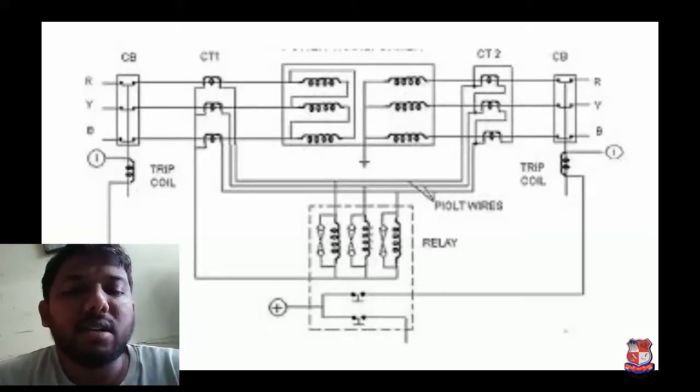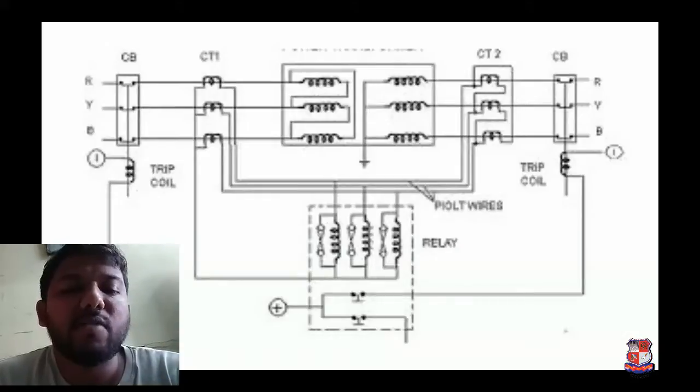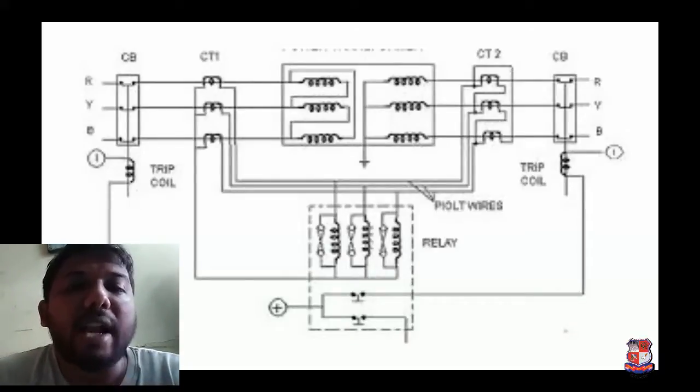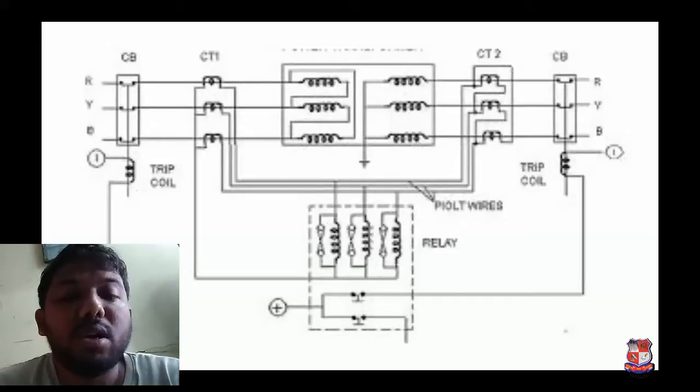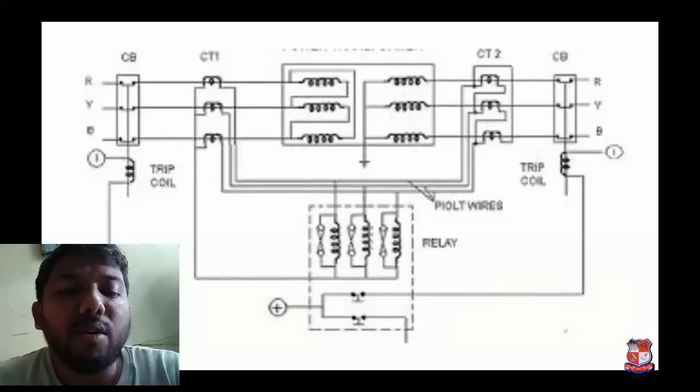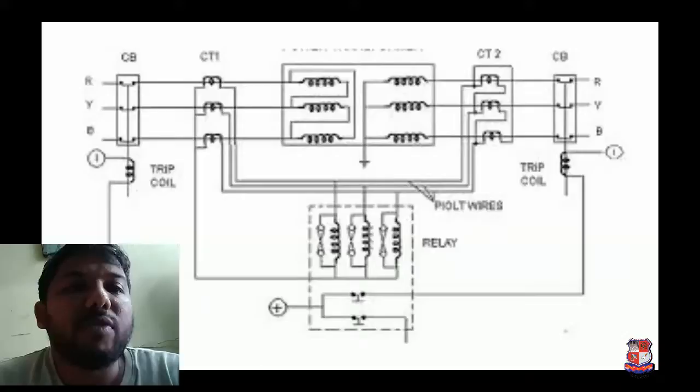It is known that the currents in primary and secondary winding of power transformer are not equal and therefore the use of identical CTs will give different currents and operate the relay even under no load condition. The difference in the magnitude of primary winding and secondary winding current is compensated by CTs of different ratio.